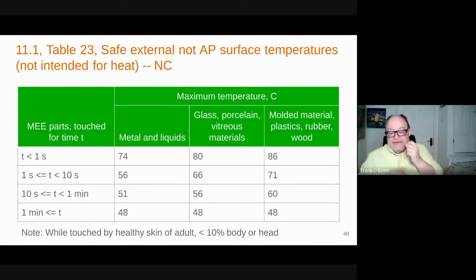So, in fact, it's considered a risk management result in the test report form, the CB test report, that the various controls are specified as falling into whatever time period and whatever limit. And we're supposed to identify that the manufacturer has done that in the test report. Either the manufacturer filling out his own report or if he hired a test lab. So the test lab will ask you for that risk management result. All right, and then if you have higher surface areas or whatever, you need to think about these things being maybe different.